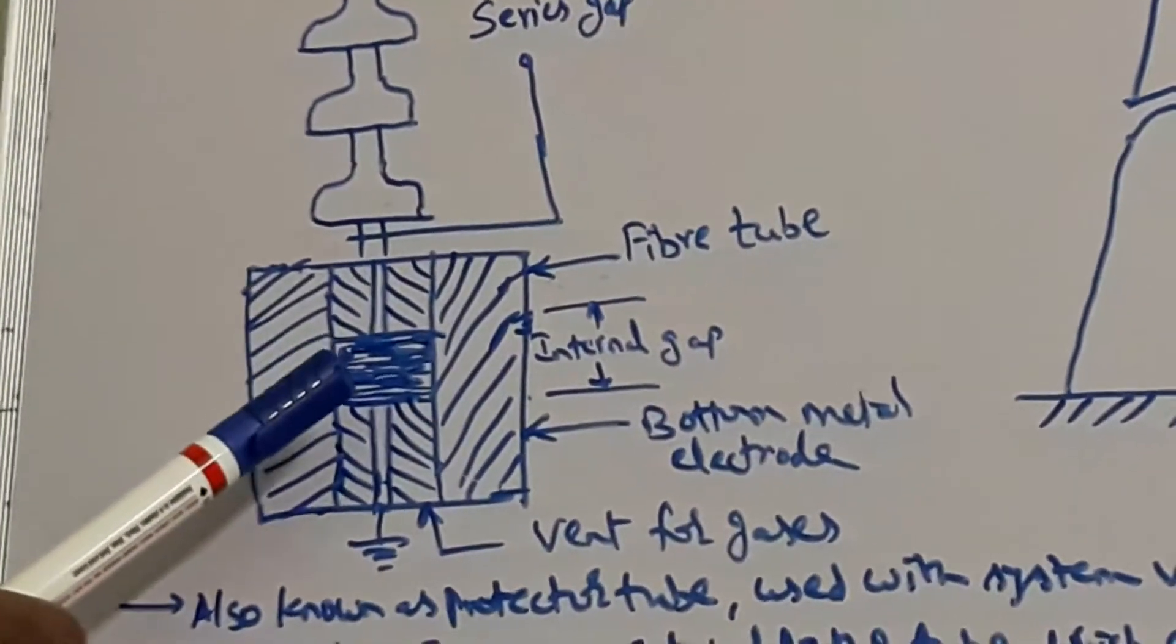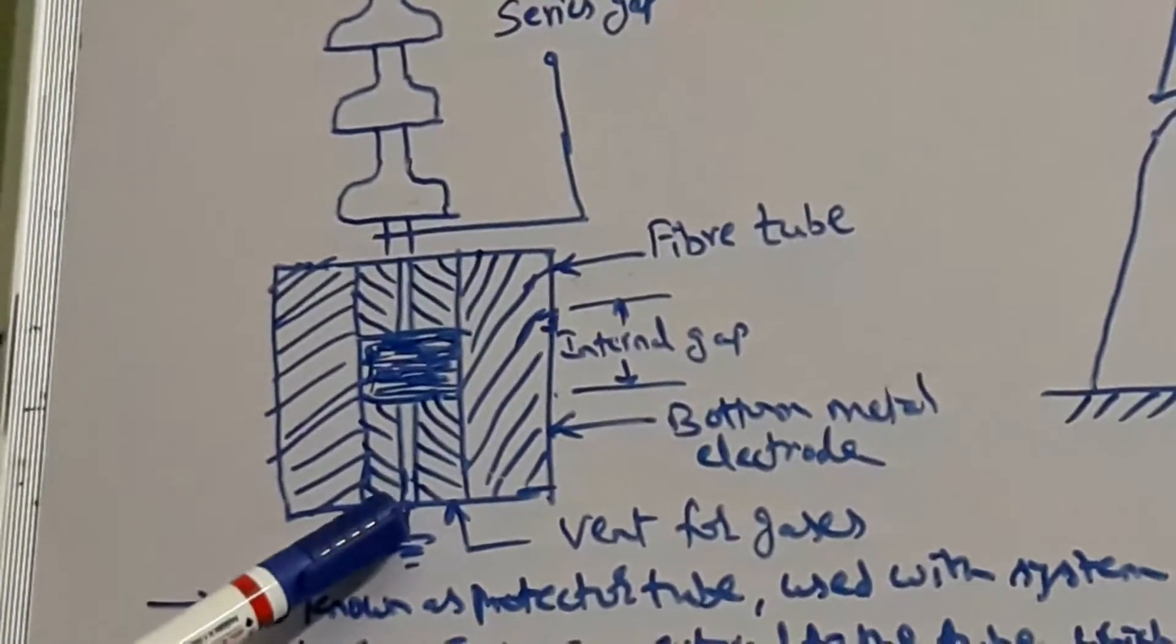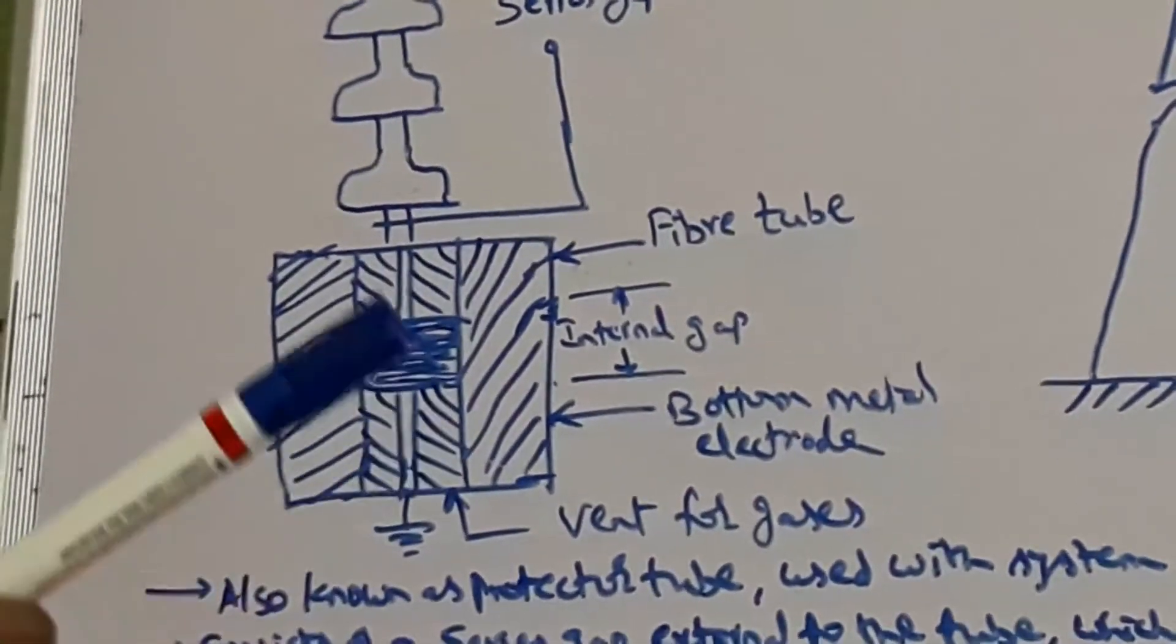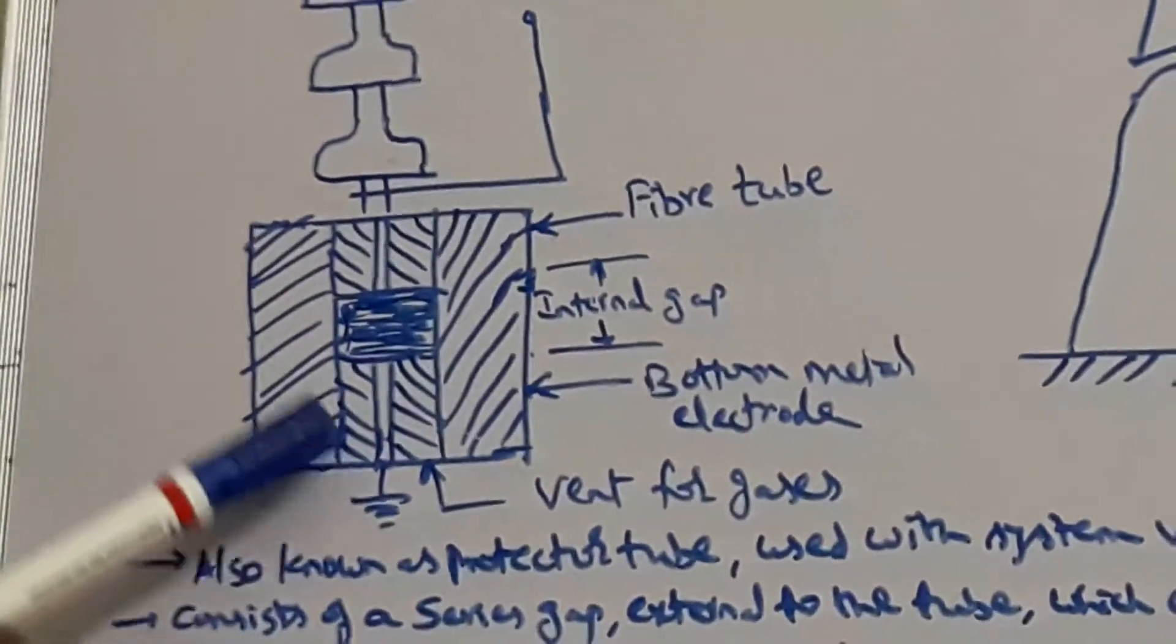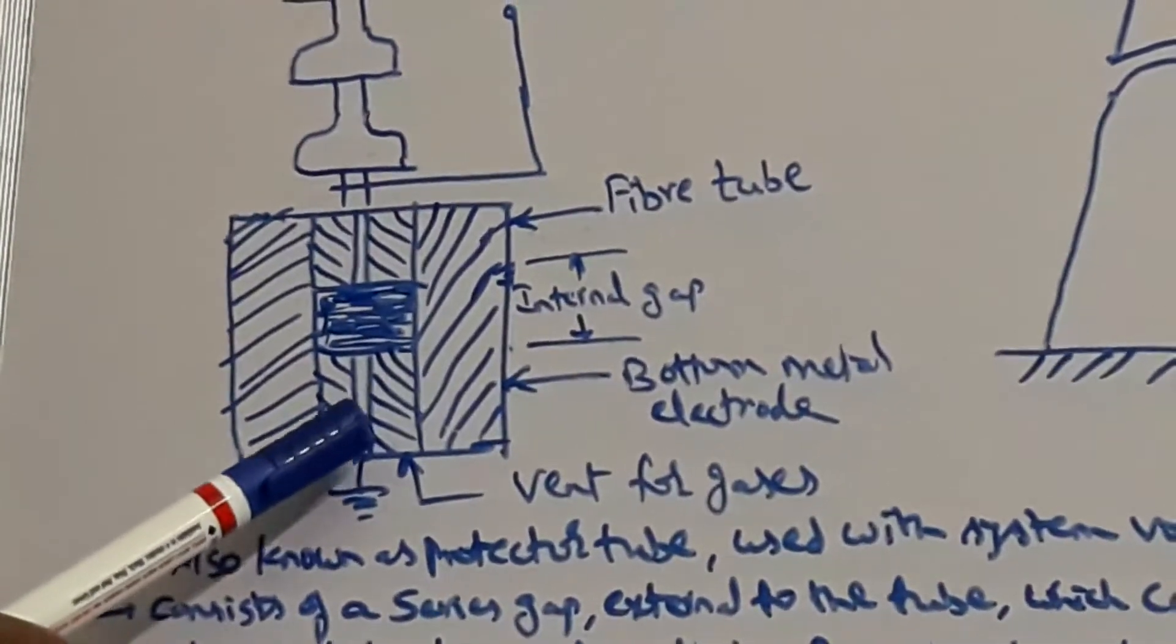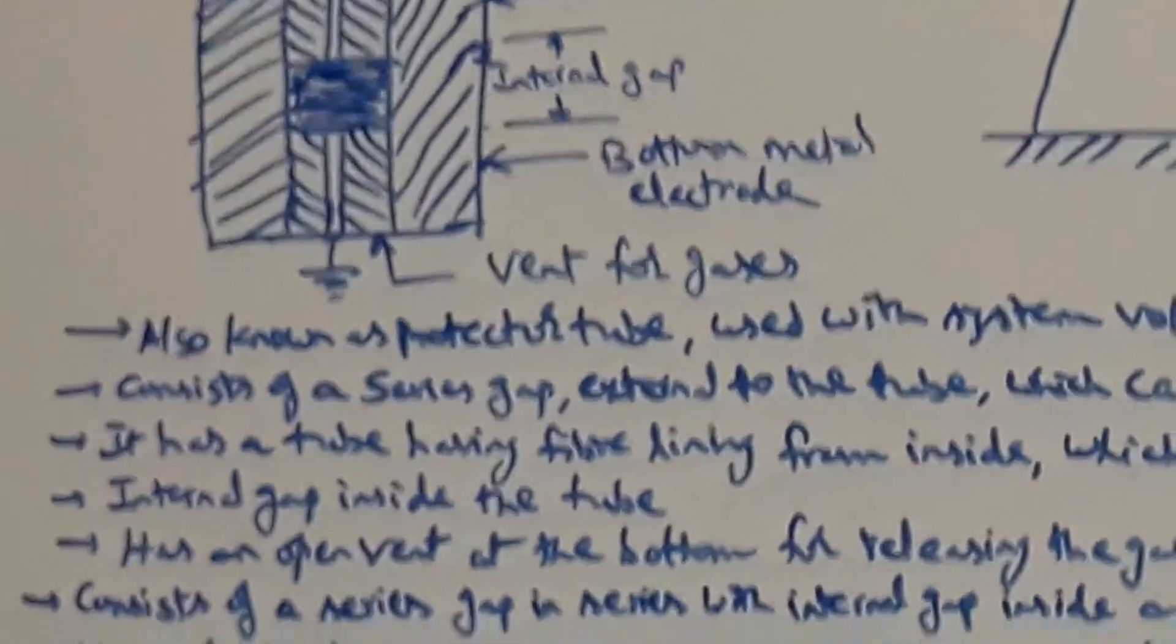The gas leaving the tube is violent and carries with it the ionized air around the arc. As it carries the ionized air, deionization of the arc takes place, and due to this deionization effect, the arc is extinguished without restriking again.